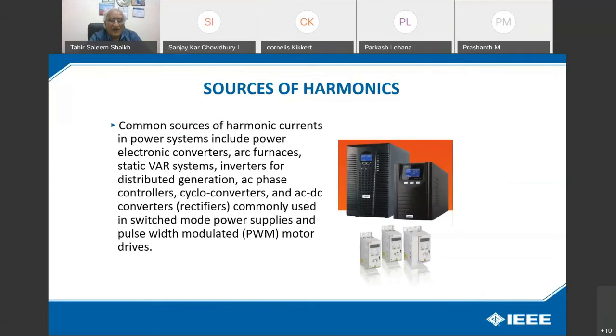Now, the common sources of harmonics are all non-linear loads. Non-linear loads in a power system include power electronic converters, arc furnaces, induction furnaces, static VAR systems, inverters for distributed generation, AC phase controllers, cycloconverters, AC-DC converters, rectifiers commonly used in switch mode power supplies, and pulse width modulation (PWM) motor drives.